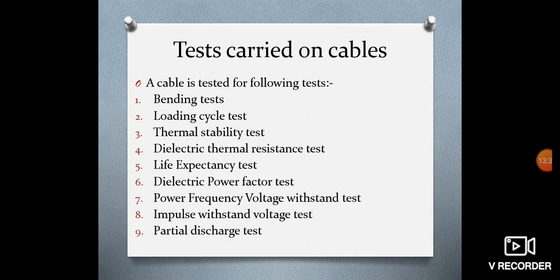Loading cycle test. A test loop consisting of cable and its accessories is subjected to 20 load cycles with a minimum conductor temperature 5 degrees centigrade in excess of the design value, and the cable is energized to 1.5 times the working voltage. The cable should not show any sign of damage. Thermal stability test. After the test carried out in the loading cycle test, the cable is energized with a voltage 1.5 times the working voltage for a cable of 132 kilovolt rating, and the loading current is so adjusted that the temperature of the core of the cable is 5 degrees centigrade higher than the specified permissible temperature. The current should be maintained at this value for 6 hours.